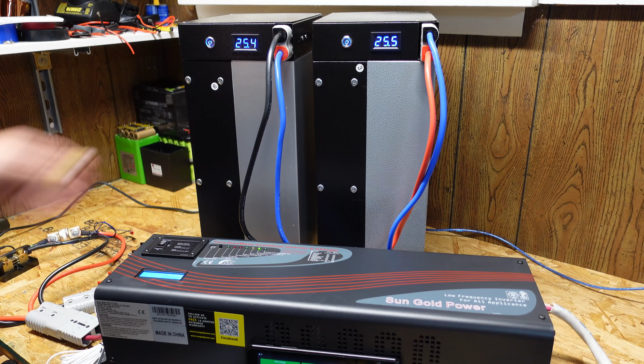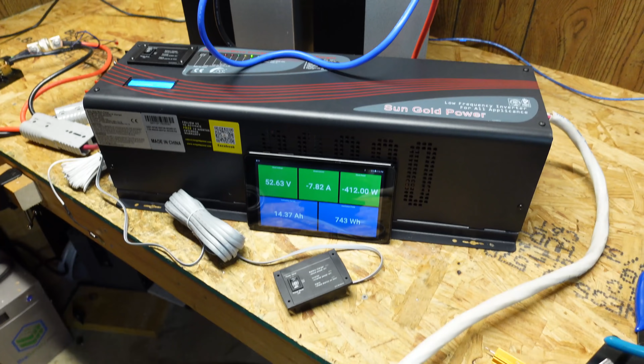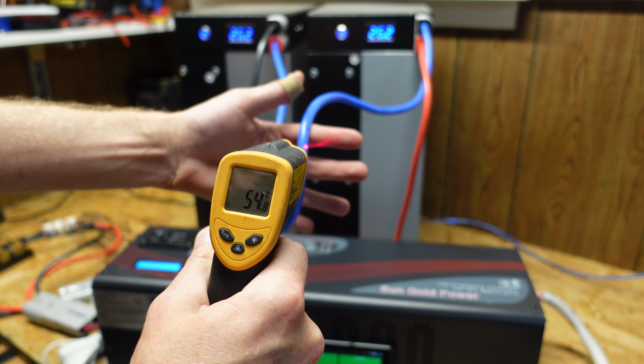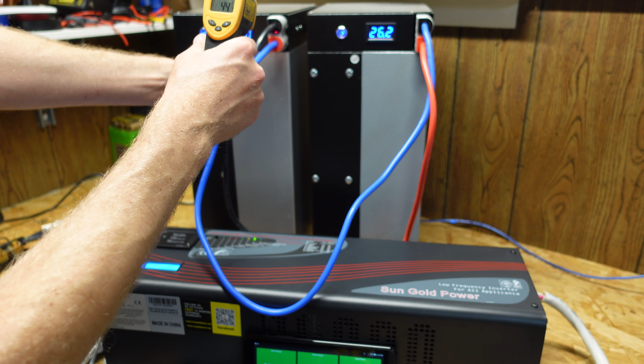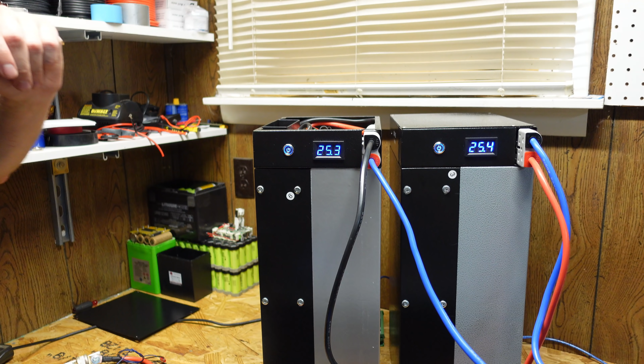These cables are very, very hot to the touch. I really wish I had my thermal camera, I didn't think to charge it ahead of time, but let's see if we can get a reading with this infrared. Oh, something shut down, the heating element in the dryer must have kicked off. We're at 7.4 amps now, we'll have to wait until it kicks back on. I see 56 Celsius, though it's hard to get an exact reading here. Oh, there it goes, it's kicking on again.